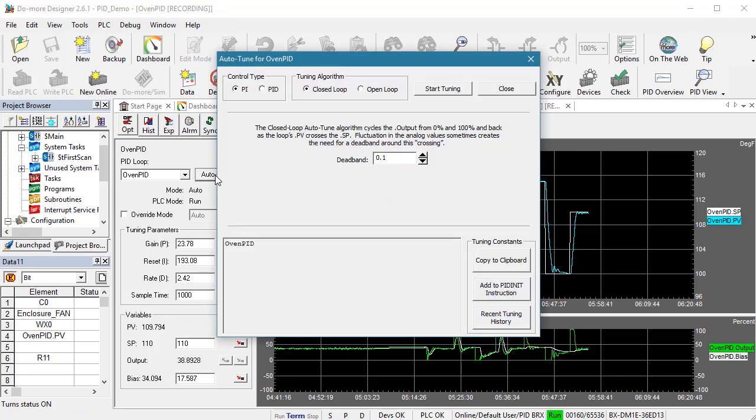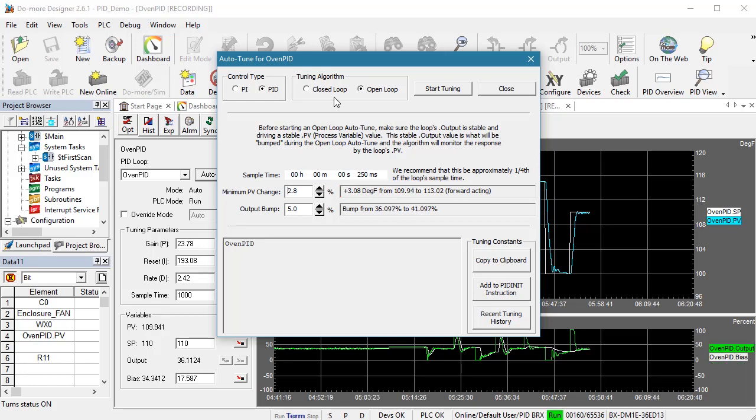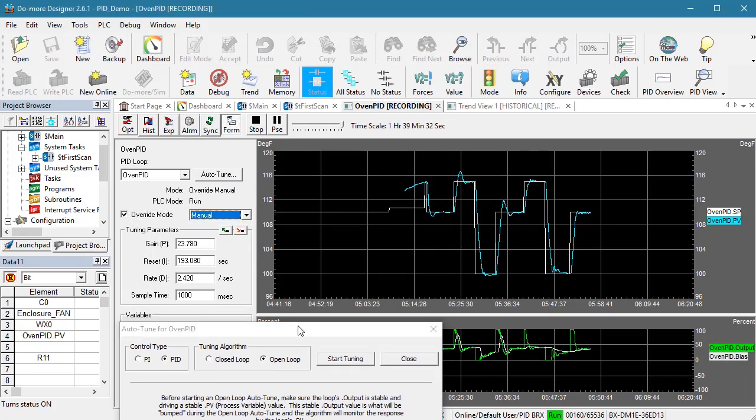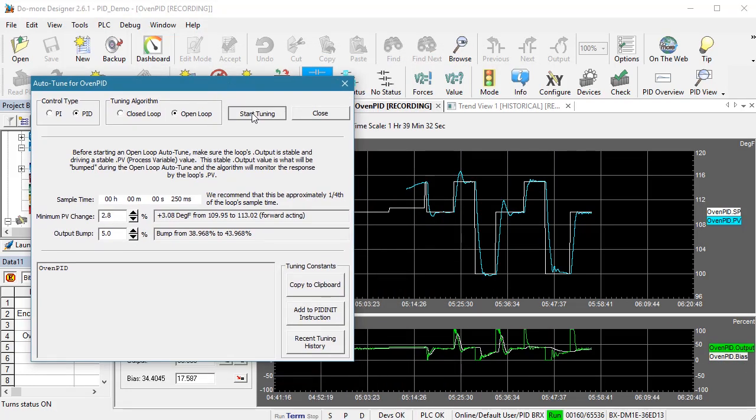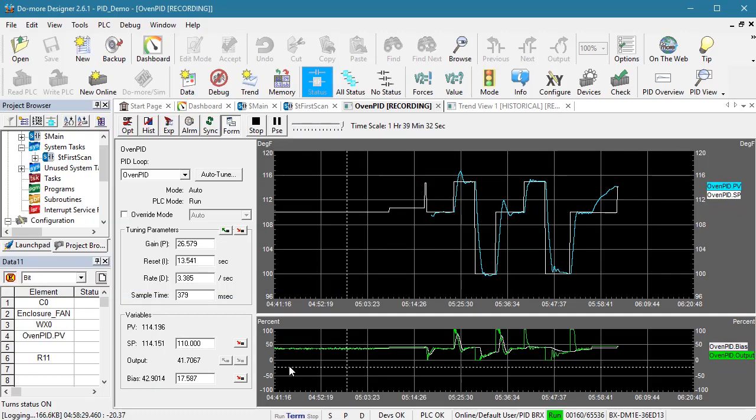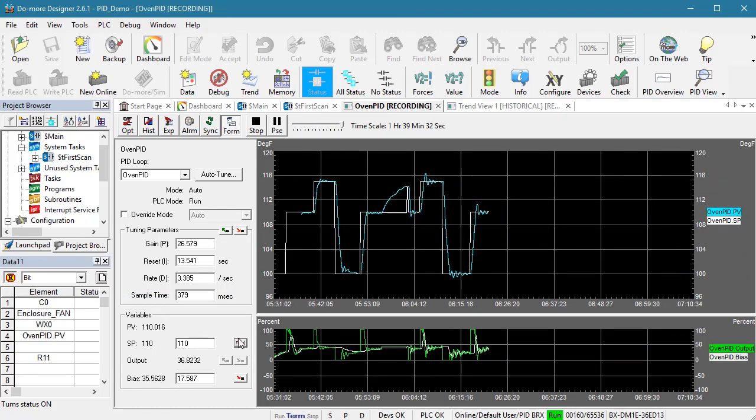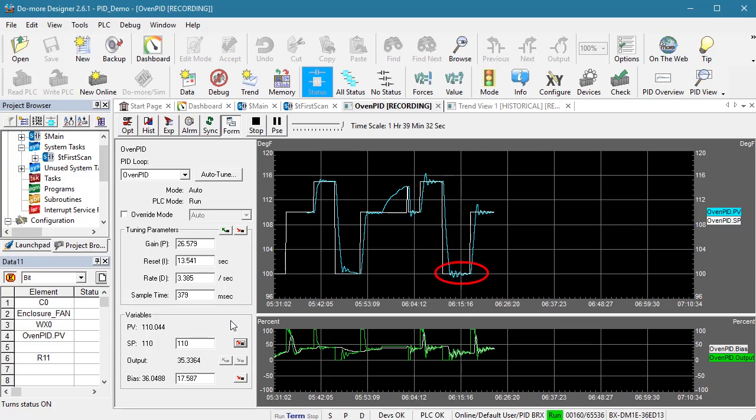Let's do one more open loop Auto-Tune except this time let's only let it rise 3 degrees and see what happens. Make sure we are in manual mode and hit start. I'll fast forward through the open loop Auto-Tune and our standard setpoints and it looks like the upswing overshoot is a little tighter, but we gained overshoot on the way down. But it still looks pretty good.